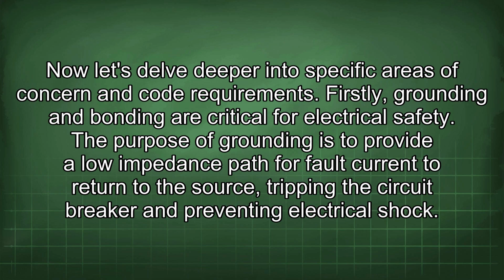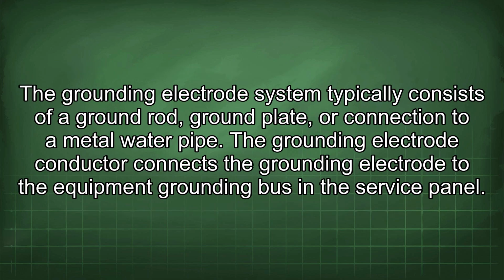Firstly, grounding and bonding are critical for electrical safety. The purpose of grounding is to provide a low impedance path for fault current to return to the source, tripping the circuit breaker and preventing electrical shock. The grounding electrode system typically consists of a ground rod, ground plate, or connection to a metal water pipe. The grounding electrode conductor connects the grounding electrode to the equipment grounding bus in the service panel.